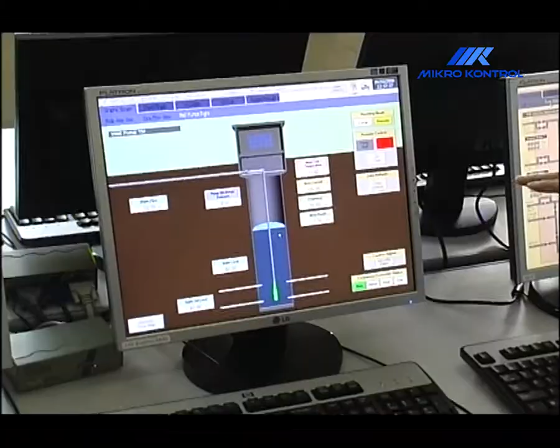This involved installing equipment into distribution cabinets, panels with the IP54 protection level, testing the panels with the installed equipment in the maintenance shop, and producing the communication software for monitoring and controlling the frequency inverters and soft starters. These panels became operational in the year 2008.